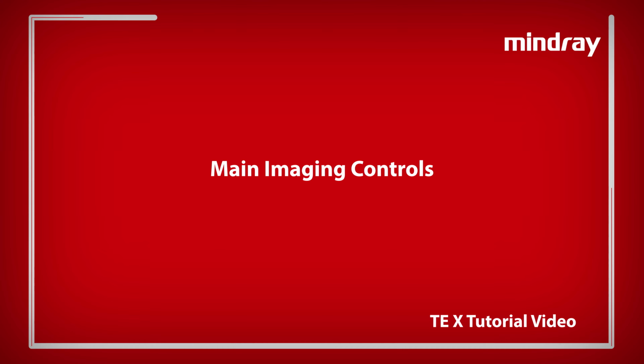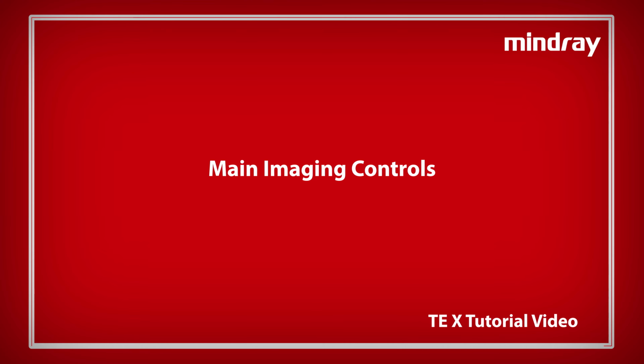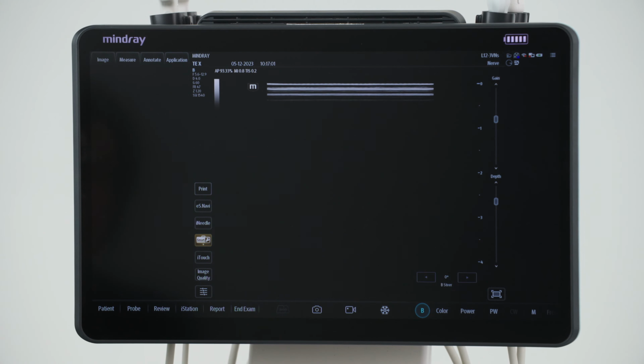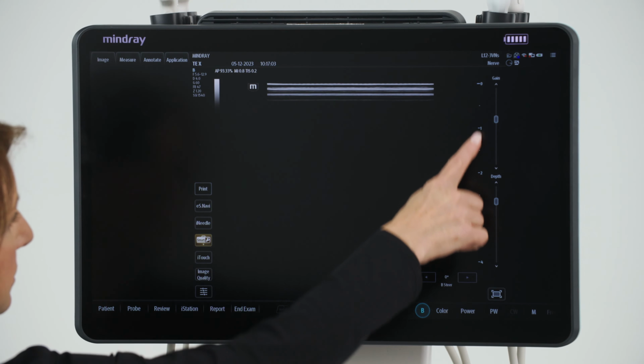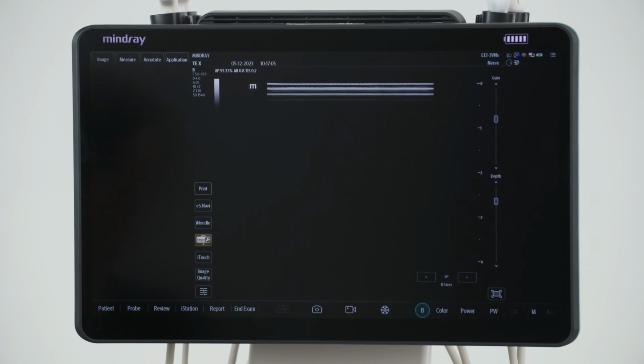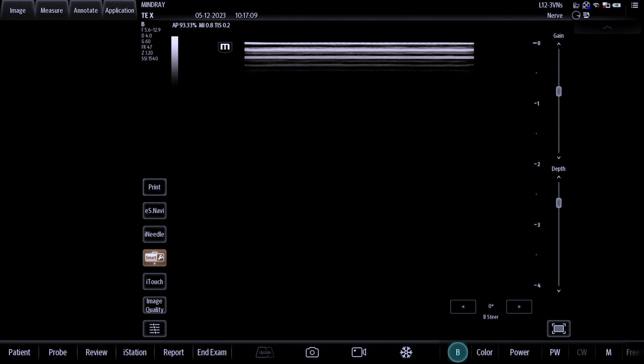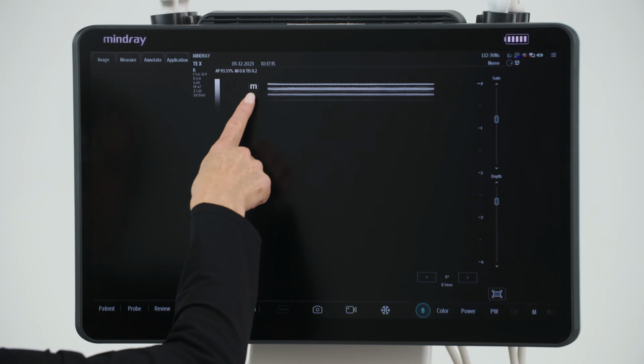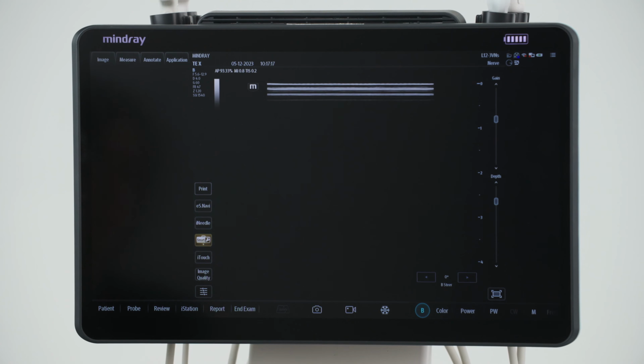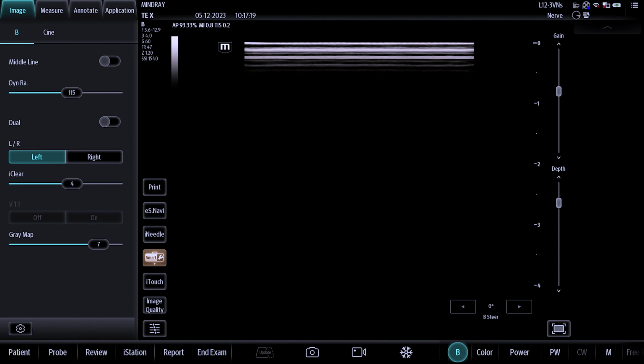Main imaging controls. The image sector features depth markers in centimeters for reference. The TE X is powered by ZST technology, so there is no focal zone marker. Rather, the image is automatically focused throughout the field of view. The M denotes the marker side of the screen. This can be switched using the left-right control under the image tab.